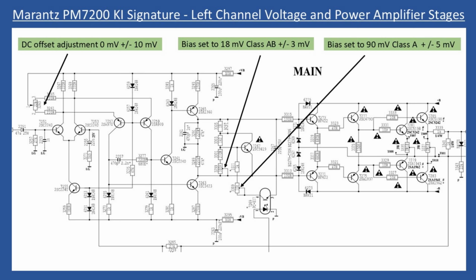And then finally, when you select Class A mode, you will see that the bias value read on your multimeter will increase significantly. And again, you will make the adjustment so you are reading 90 millivolts, but with a tolerance of plus or minus 5 millivolts.